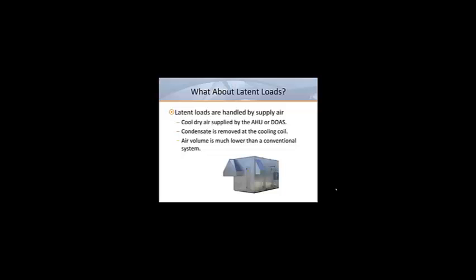So how do chilled beam systems address latent loads? It's handled by the supply air. Cool dry air is supplied by the air handler or dedicated outdoor air system and condensate is removed at the cooling coil. This means that the air volume is often much less than that of a conventional system with overhead diffusers because it only has to meet the ventilation and latent heat removal requirements. This results in smaller ductwork and possibly lower system static pressures.